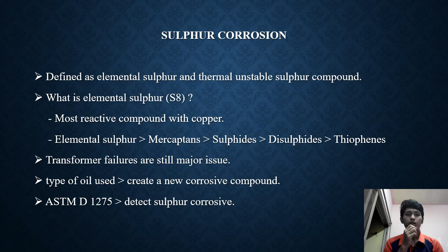For sulfur corrosion, transformer failure is still a major issue. It is suspected that the type of oil used can create a new corrosive compound. Due to this reason, the ASTM D1275 method can be used to detect corrosive sulfur.